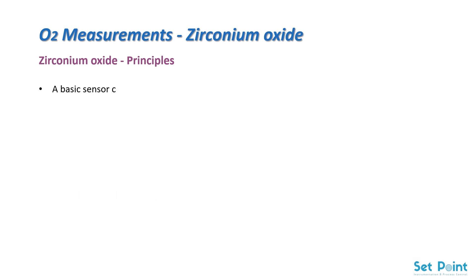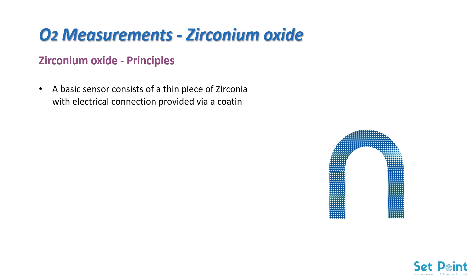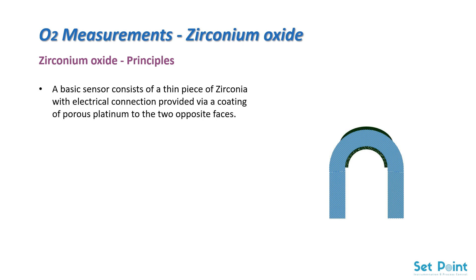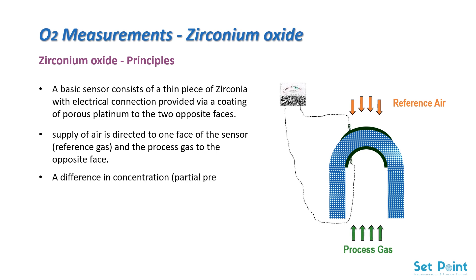A basic sensor consists of a thin piece of zirconia with electrical connections provided via a coating of porous platinum to the two opposite faces. A supply of air is directed to one face of the sensor as a reference gas, and the process gas to the opposite face. A difference in concentration — partial pressure — of oxygen on each side of the zirconia produces a millivolt signal.